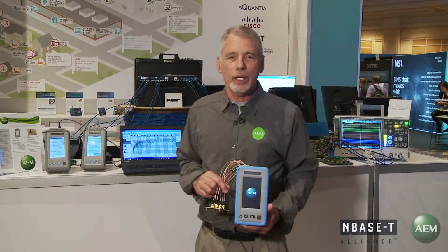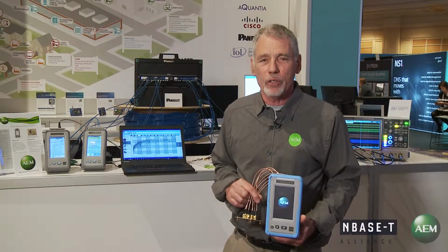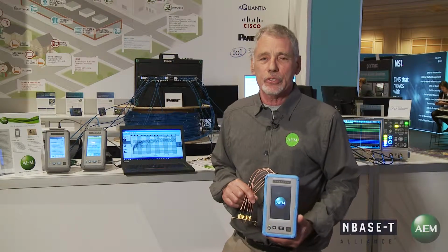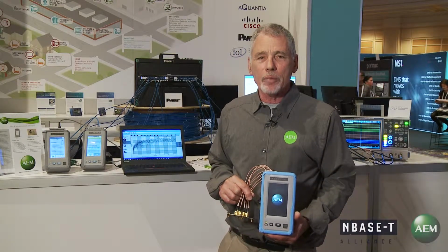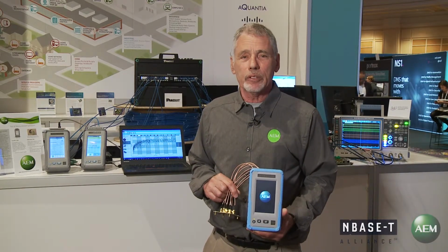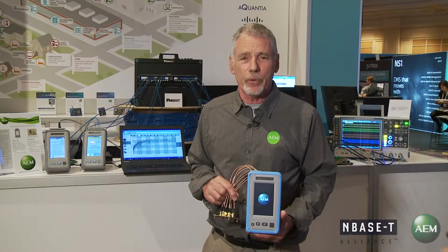I'm going to talk about the AEM mixed mode vector network analyzer. Effectively what the vector network analyzer does is it makes measurements of all of the impairments for all of the cabling infrastructure from 100 kilohertz to 3 gigahertz. It's an optimized device and particularly targeted at automotive and data rates associated with all of the Ethernet cabling technologies, including category cabling as well as all of the copper interconnects.